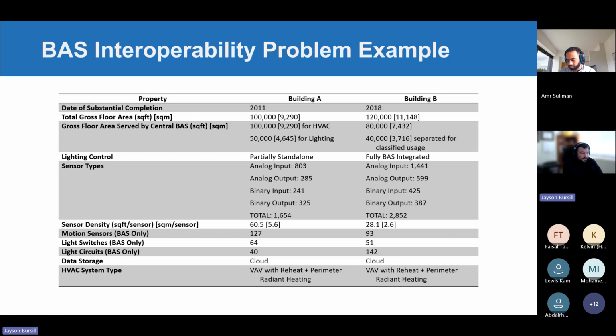However, where the industry is right now, there are some gaps, and I like to present this case study where I got a bit frustrated with a lighting system. So building A here has lighting as a separate standalone system. Both of the buildings were intended to be fully BACnet and have everything on a flat IT network on BACnet. But in this case with building A, the lighting was on a standalone proprietary system. It had a BACnet device at the top of the system, but that BACnet device wasn't actually able to route traffic from the underlying lighting system.